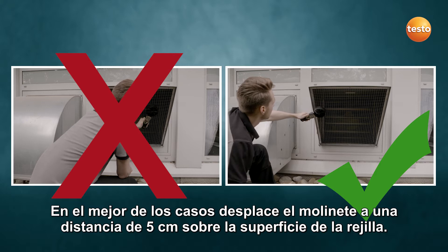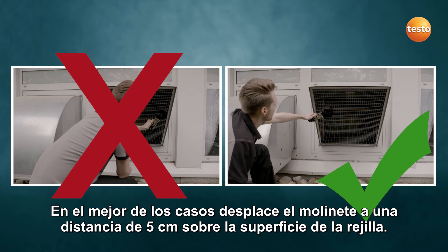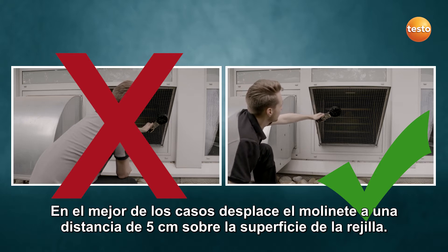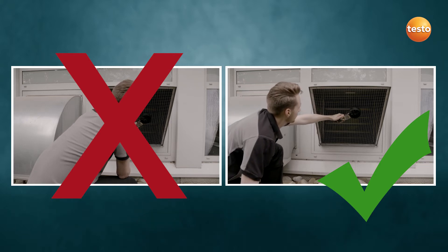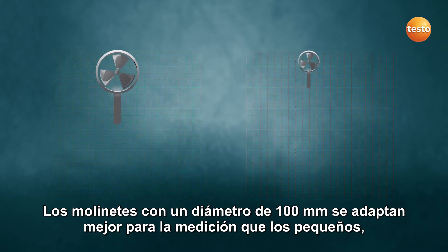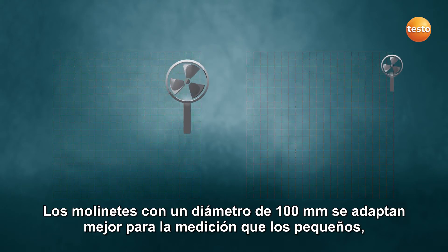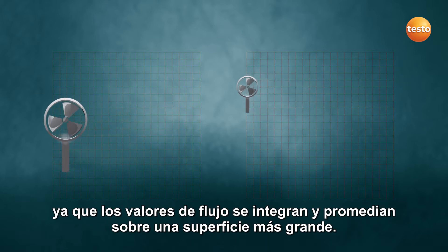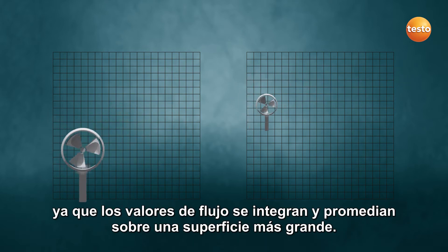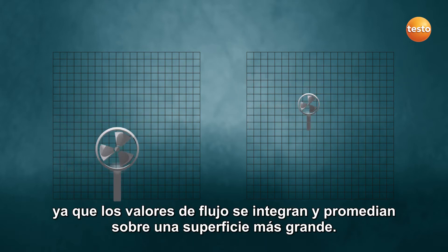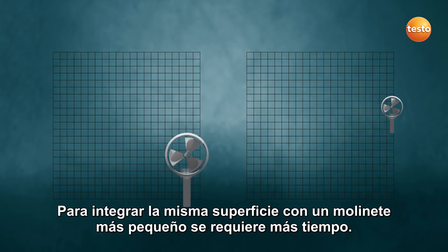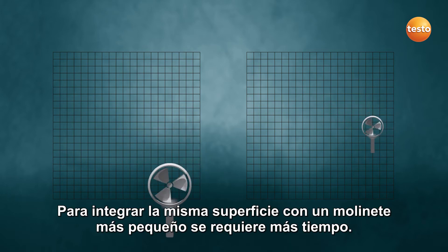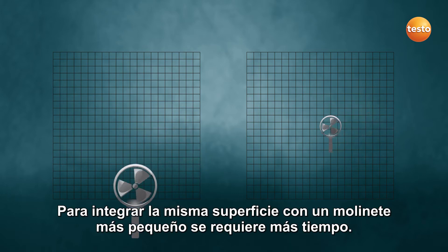The best method is to move the vane across the grill surface at a distance of 5 cm. Vanes with 100 mm diameter are better suited to measuring than instruments with smaller vanes, as the flow values are integrated and averaged over a larger area. Integrating the same area with the smaller vane takes significantly longer.